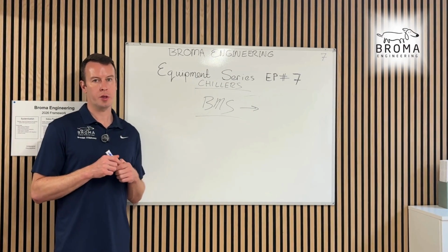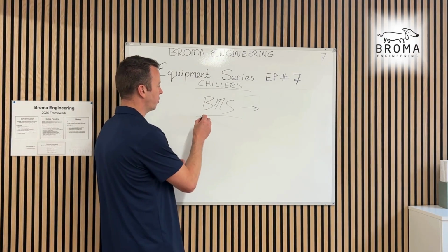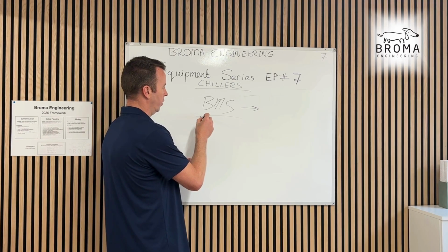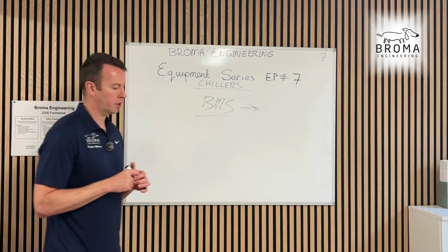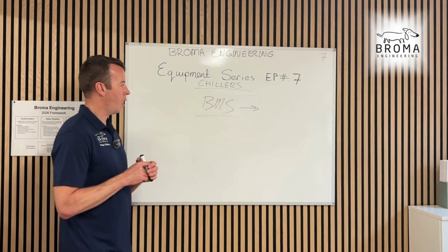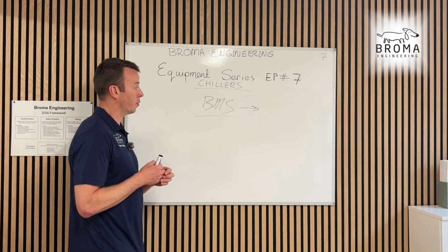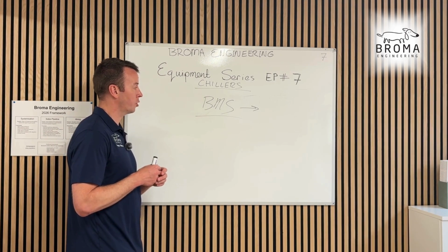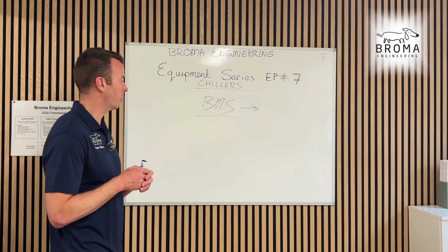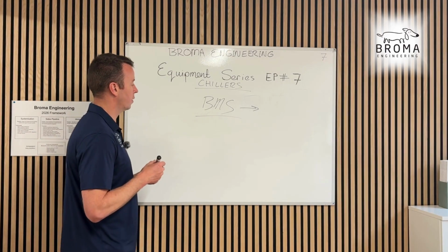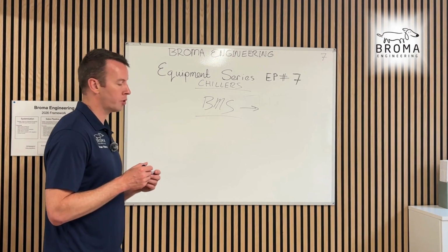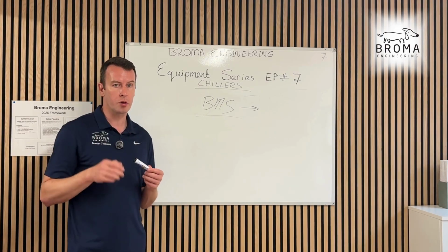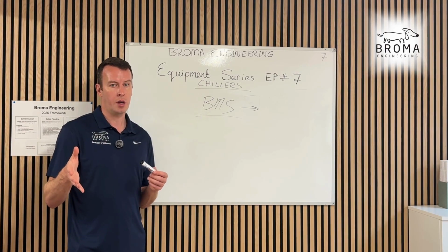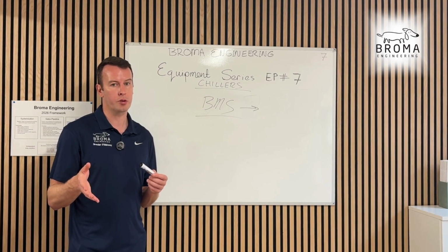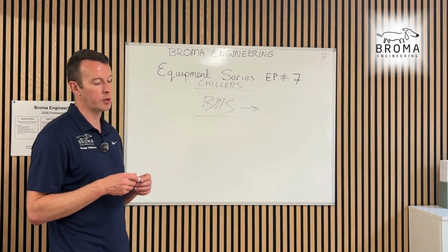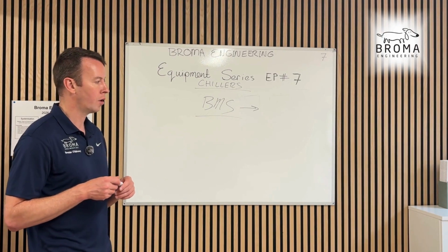Okay, the next thing is BMS. You need to make sure your BMS cables, your comms cables, are connected, tested, ready to go, and back into your BMS panel. There'll probably be a BMS panel on the chiller, and then there'll be a BMS panel up there somewhere, and then back to the head end. So talk to your BMS manager, make sure they're on schedule. In the morning meetings, the BMS team has to be asked: are you on schedule? Go down and walk it, make sure. They might tell you it is, but the BMS contractor needs to be on the ball.